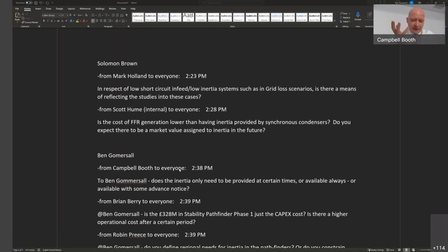There was a question that I asked, or maybe more of a comment, that I'm not sure anyone directly responded to. And I genuinely don't know. This might be a silly question, but if a synchronous compensator or condenser provides inertia, and there's a frequency dip in the system and the frequency still drops significantly, the rate of change of frequency might be slowed down. But as the system begins to accelerate, is it disconnected, or is it accelerated up with the rest of the system? Because if it's accelerating up with the rest of the system, it's providing a bit of a drag as the system tries to return to nominal frequency, or perhaps the friction is so low that it's not an appreciable real power load when it's accelerating. I don't know if anybody's thought of that one.